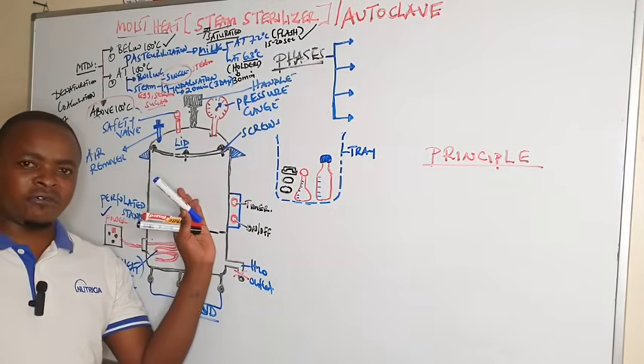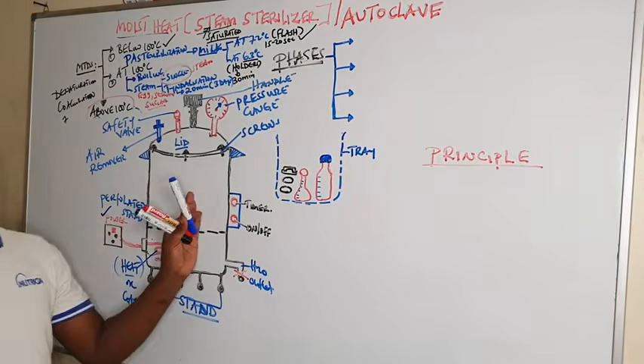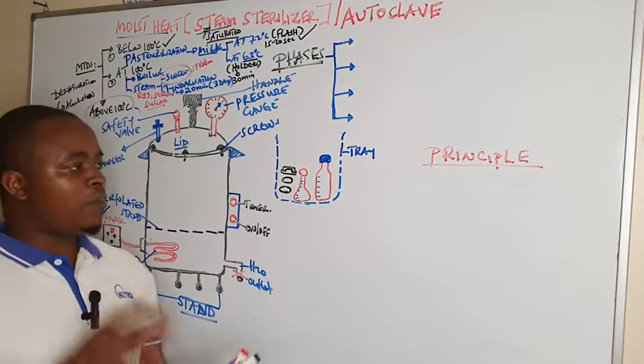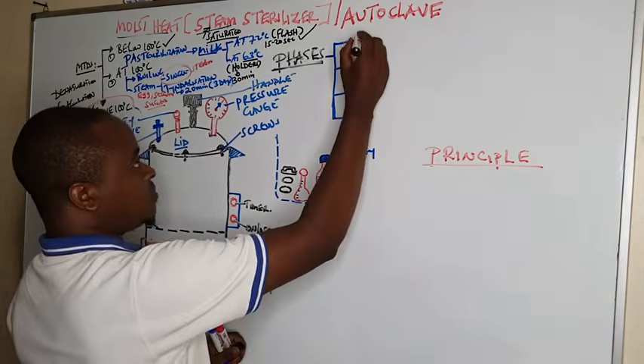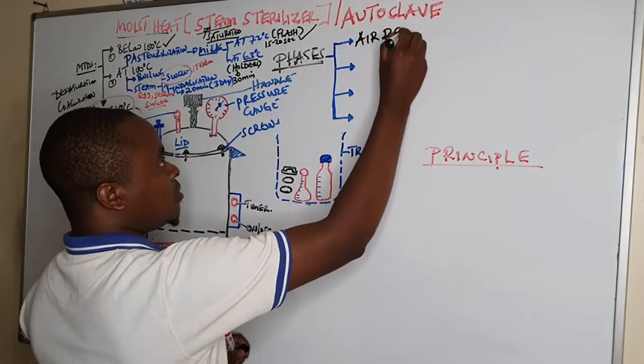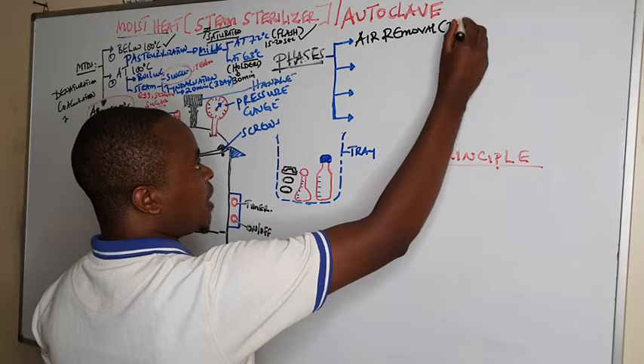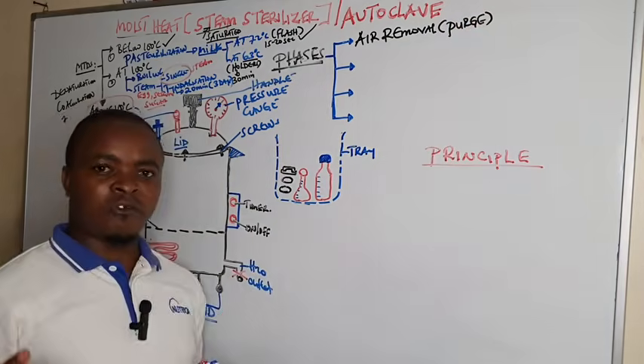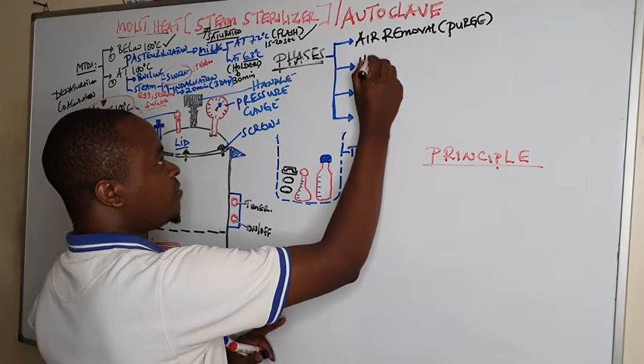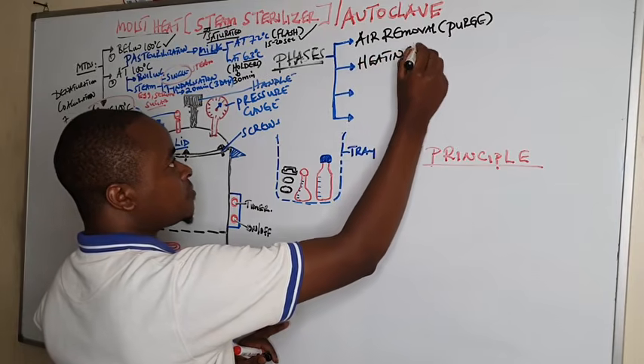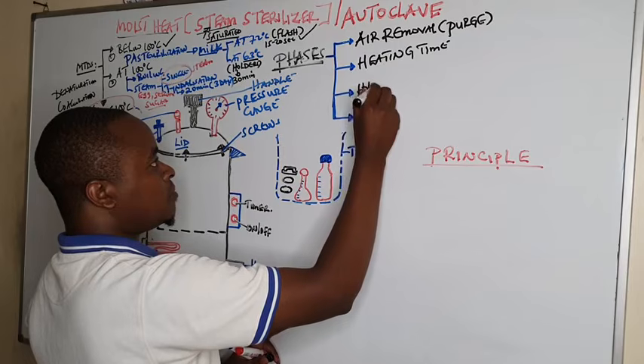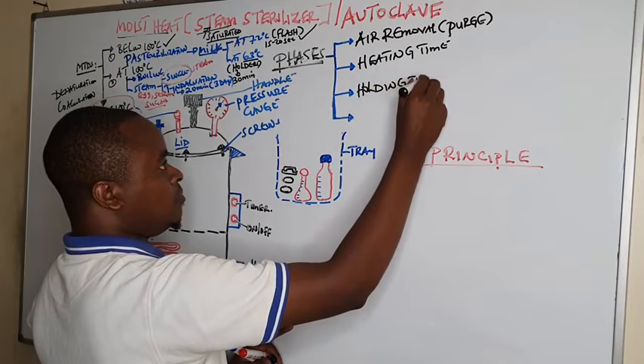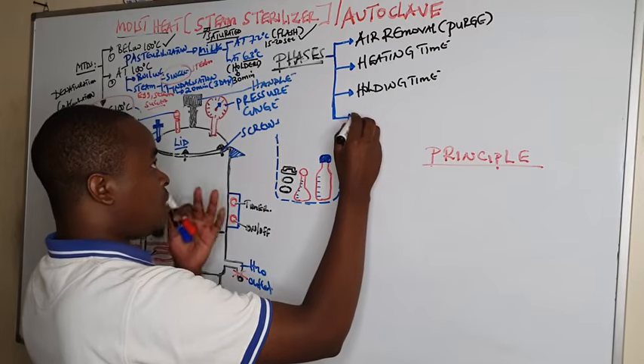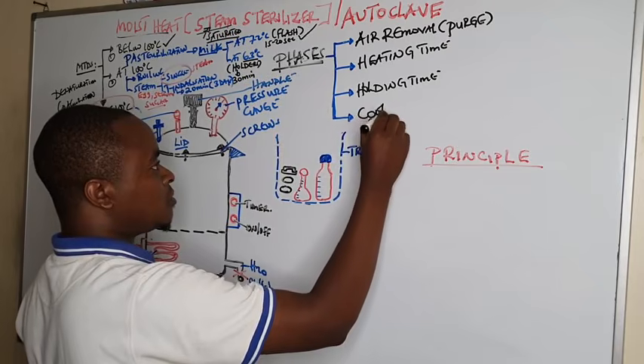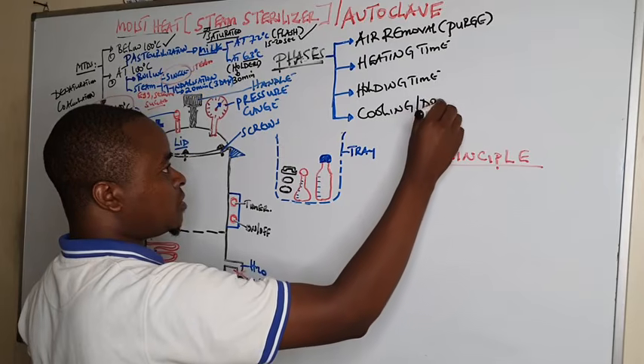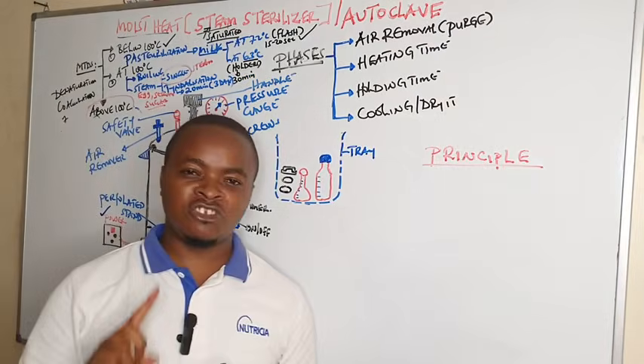And this is sterilization by autoclaving, where we are using a temperature above 100. It contains phases, or you can call them stages. Phase number 1 you can call air removal; some books call it the purge phase. So air removal phase or purge phase. Then we have the heating time phase. Then we have the holding time. Then we have what we call the cooling, or you can call it drying. So these are the 4 phases under the sterilization cycle.